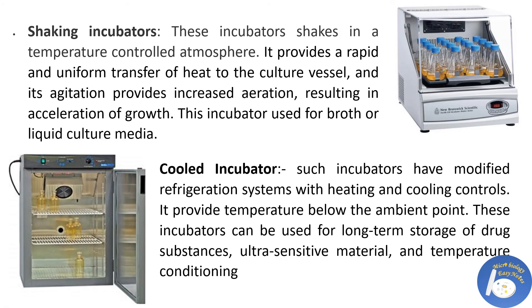Shaking incubators shake in a temperature-controlled atmosphere, providing rapid and uniform transfer of heat to the culture vessel. Their agitation provides increased aeration, resulting in acceleration of growth. This incubator is used for broth or liquid culture media. Cooled incubators have a modified refrigeration system with heating and cooling controls, providing temperatures below the ambient point. These can be used for long-term storage of drug substances, ultra-sensitive materials, and temperature conditioning.